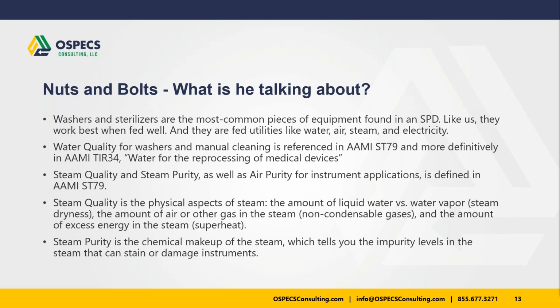What is this stuff? Steam quality, you're looking at how much water is in the steam, condensate, that's your steam dryness. Water vapor is what you want to have. Water is not going to do sterilization very well for you. Then there's the amount of air or other gas in the steam, again, a terrible sterilant, air or anything other than steam being in the steam. And superheat, well, that's the one that comes up and bites you, because that's the one that will either burn through filters or melt plastics. It's very rare, but when it happens, boy, is it spectacular.